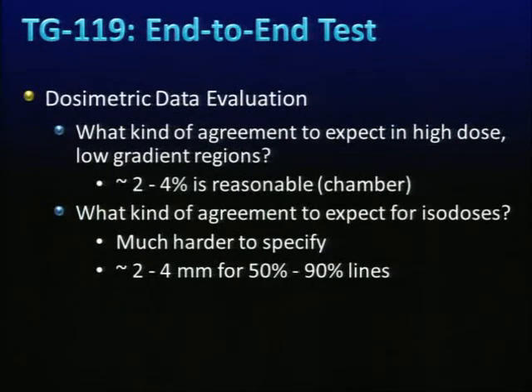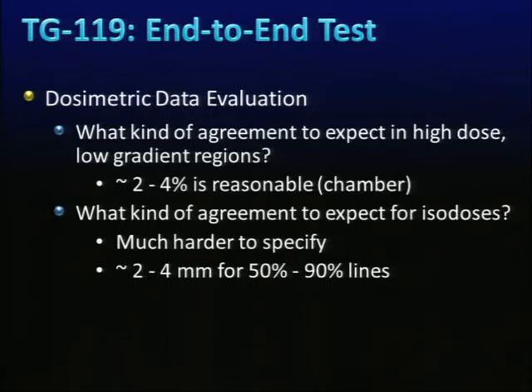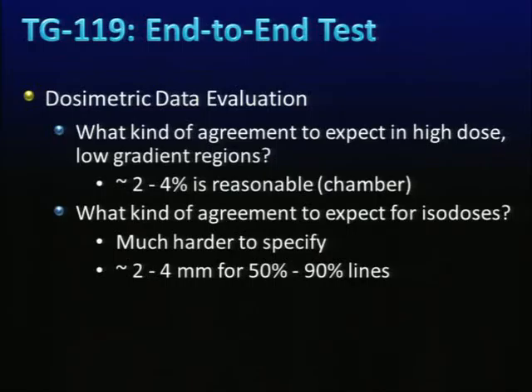For evaluating end-to-end test results, in high-dose, low-gradient regions, a 2–4% dose difference with the chamber is reasonable. TG-119 recommends the 50% to 90% isodose line should show 2–4 mm agreement. TG-119 provides mock cases including head and neck, prostate, and spine, which can be used directly or adapted; IMRT and VMAT-specific cases can also be added.